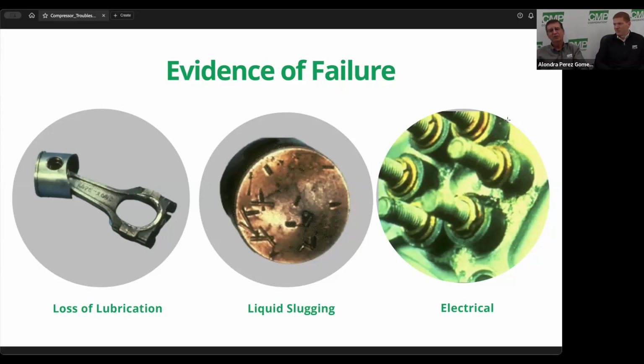Always make your electrical connections metal to metal. A lot of times, Carrier has insulators, especially on their 06E compressors, and we have a lot out in the field where they just put their lead wire down on top of the insulator and then put a nut on top of it. Well, then that post eventually gets hot because you can't get it tight enough to make a good connection there when you're going to pull something like 40 and 50 amps on one leg.